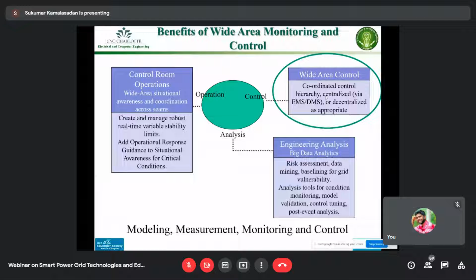So one way that measurement and control has improved, based on phasor measurement unit integration, is what we call wide area control. This means that because of measurement devices like phasor measurement units in different parts of the system, we now have the capability to monitor and control the grid as a whole, not as separate parts. In general, this is known as wide area control or coordinated control.